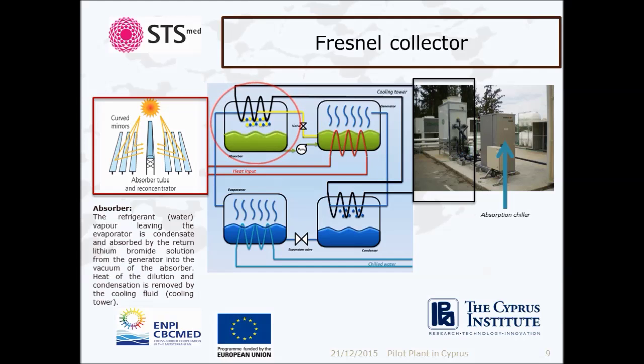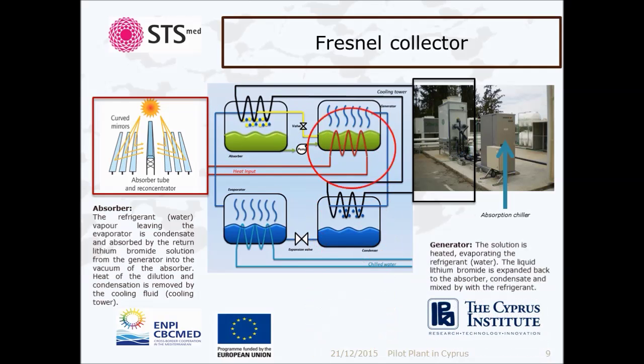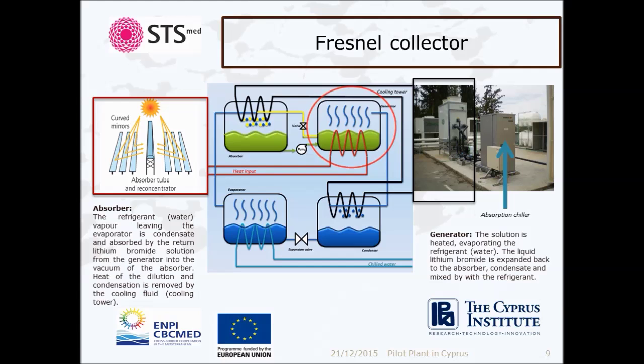Heat of the dilution and condensation is removed by the cooling fluid from the cooling tower. The generator: the solution is heated by the heat produced by the Fresnel collector, and then the refrigerant water evaporates. The liquid lithium bromide is expanded back to the absorber, condensed and mixed with the refrigerant. The cycle is then the same as a classical refrigeration in the condenser and the evaporator.